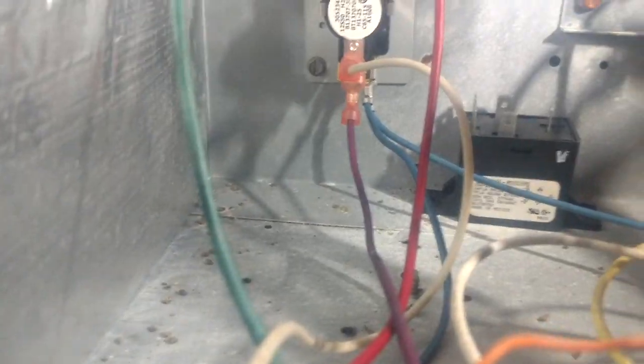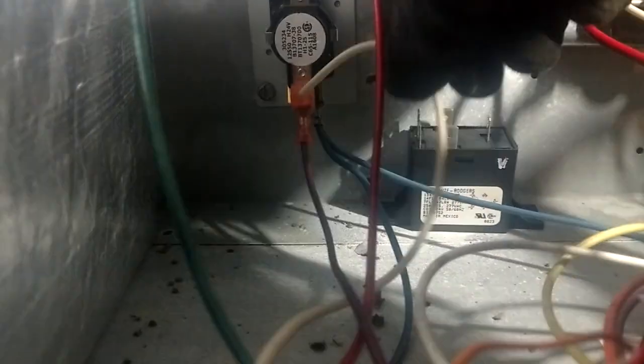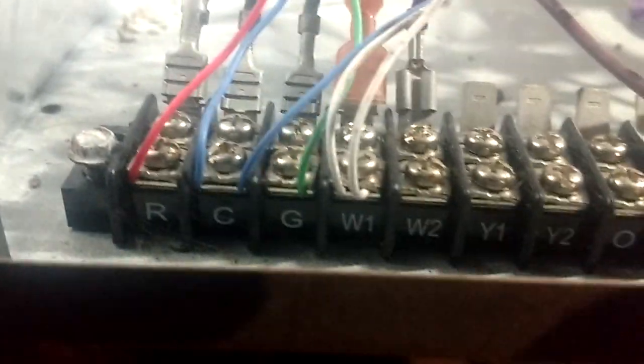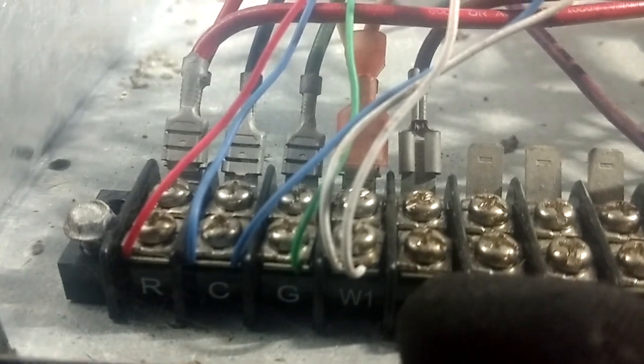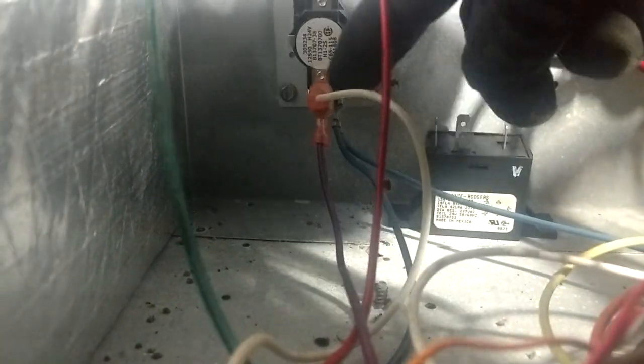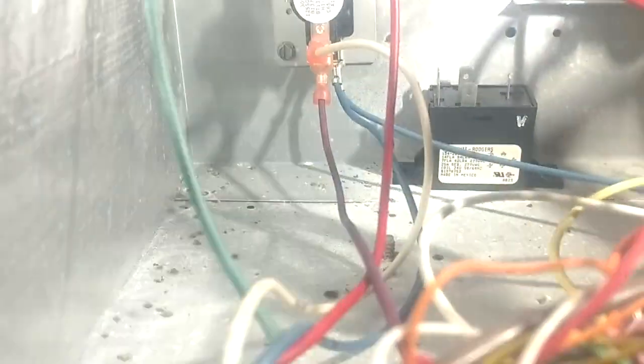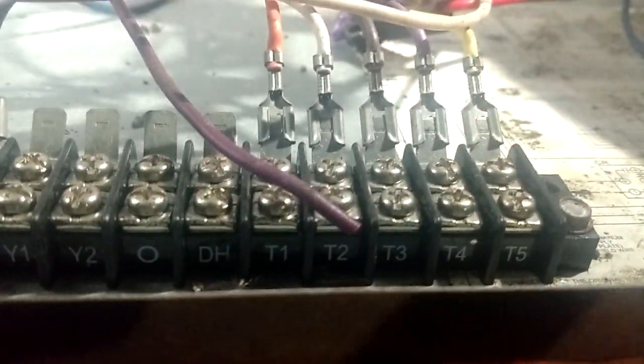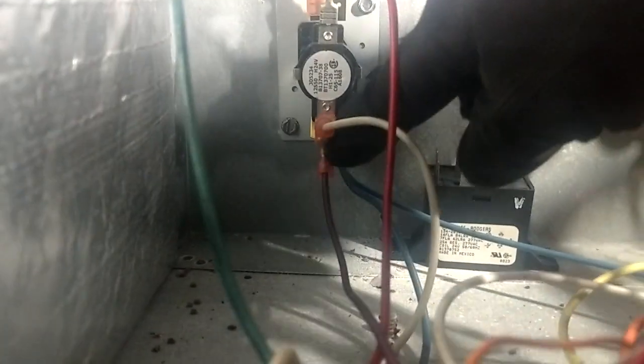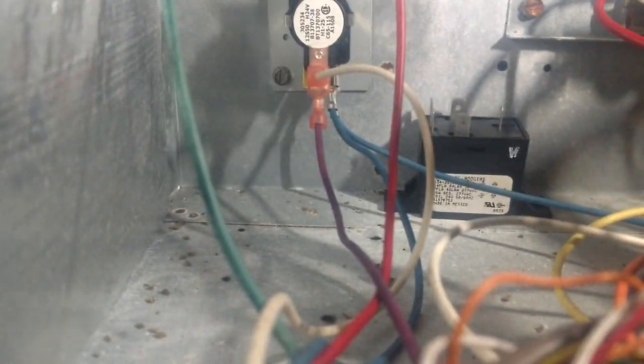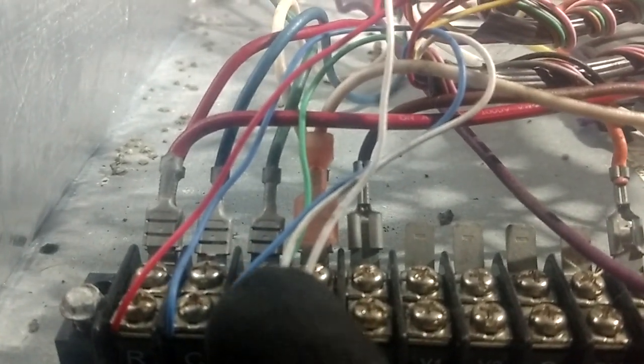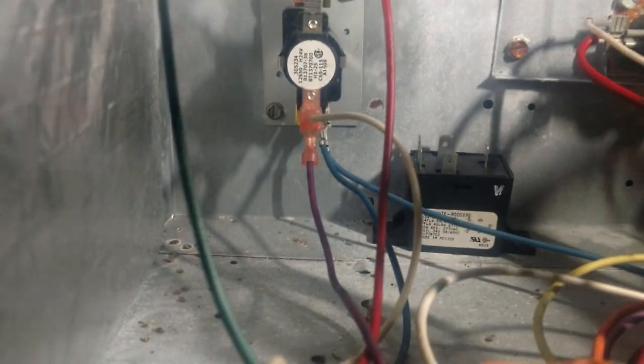And the way this particular relay is working, if you see, we have a white wire up here on the top, and that comes back to the W terminal right here. That is on a normally closed switch to the wire underneath it, which is the purple, and that comes back to a T2 terminal, which goes to a white wire that is going down to power the speed tap for the blower. So that is our normally closed set of contacts on that relay. So if you ever get a call for the electric heat to come on and you get power here on your white wires, you have to have the blower on.